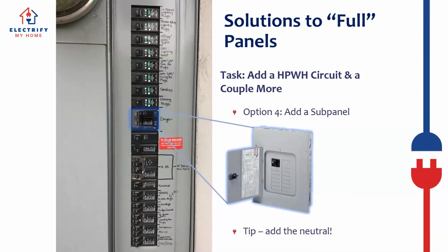Another space-saving option: if we've got plenty of capacity in the panel from our load calculation, a great option is to add a sub-panel. This is an important way to help the customer plan ahead. We often run sub-panels that we put all the new electrified appliances on. For example, we'll take the dryer circuit, replace it with a sub-panel, place the dryer circuit in the new sub-panel, as well as any new circuits we need to feed. Again, to do this we want to ensure we have sufficient capacity in the main panel to begin with.